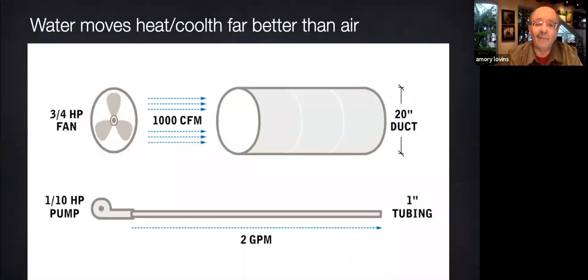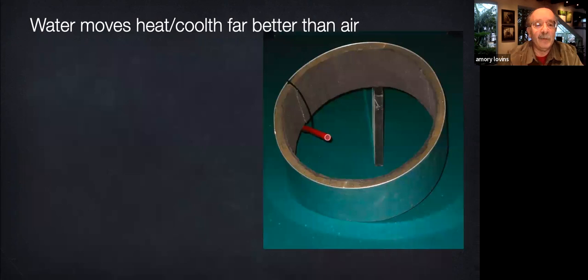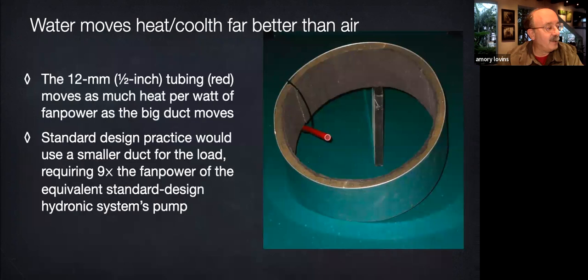Peter Rumsey offers 3 lovely illustrations of why it's better to deliver heating or cooling via water than via air. First, a 1-inch tube with a 1/10 of a horsepower pump delivers the same heating or cooling flux as a 20-inch duct driven by a 3/4 horsepower fan. How much is 3/4 of a horsepower? Well, just visualize a medium-sized horse working hard and never resting. Ease the task and earn good horse karma. Here's a visual version of that story with slightly different numbers, which depend on the temperature difference.